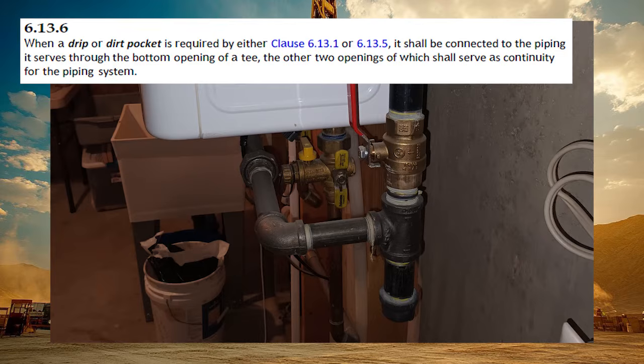Next, clause 6.13.6 deals with orientation. When a drip or dirt pocket is required by these two clauses, it shall be connected to the piping it serves through the bottom opening of a T, the other two openings of which shall serve as continuity for the piping system.